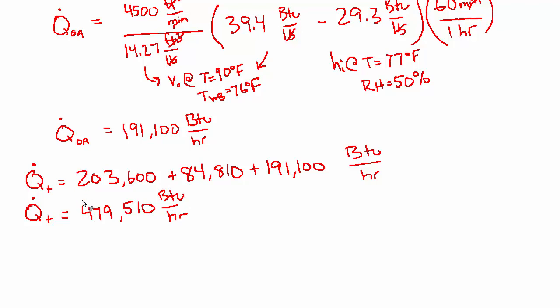And they asked us for the tonnage, so let's just convert that to tons. There are 12,000 BTUs per hour per ton. So BTUs per hour cancels, and we should be left with tons. And that's about 40 tons. And that's answer C.